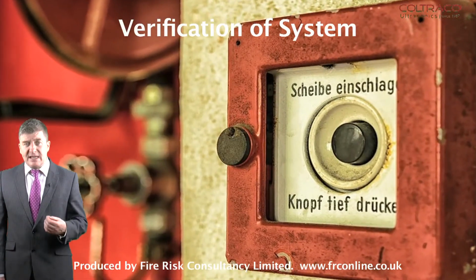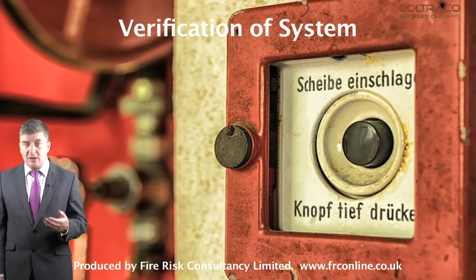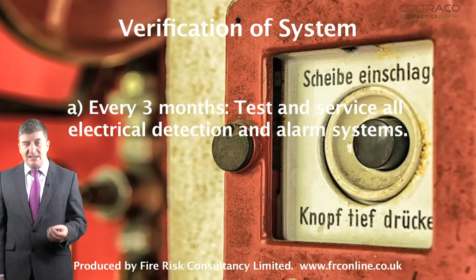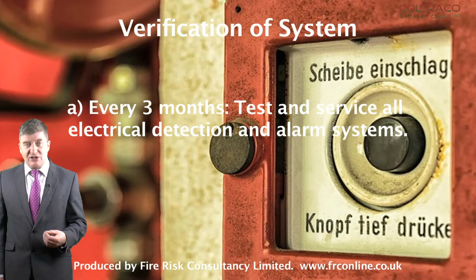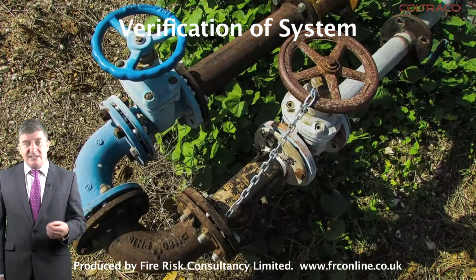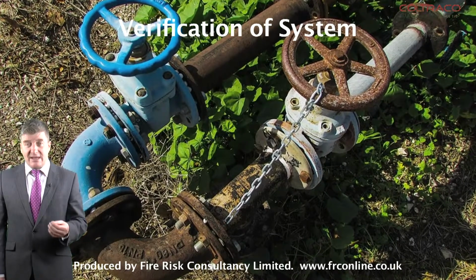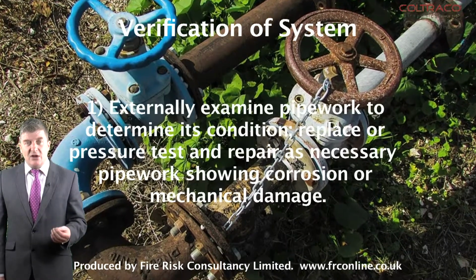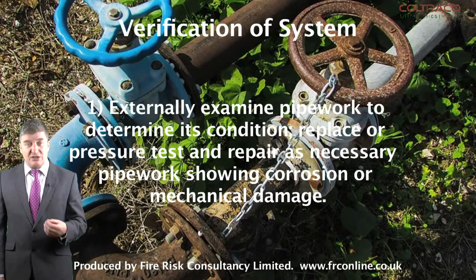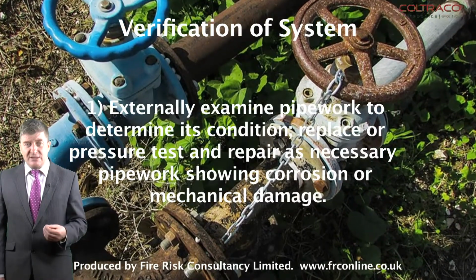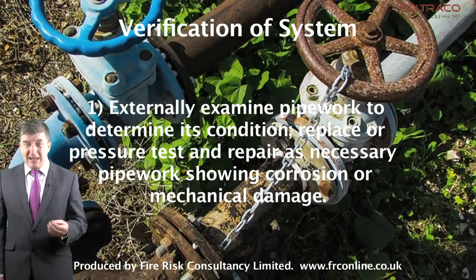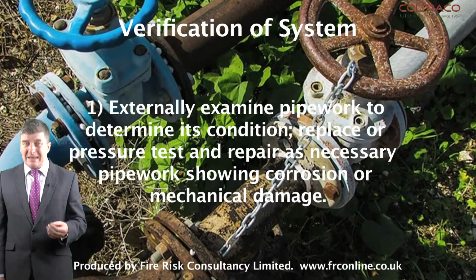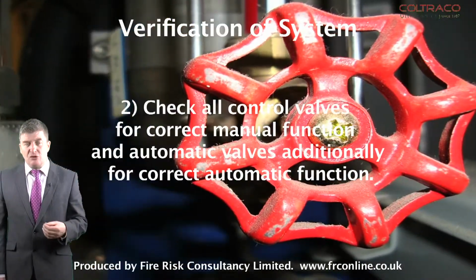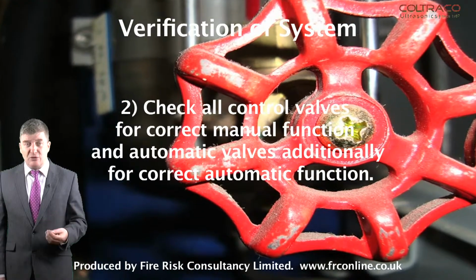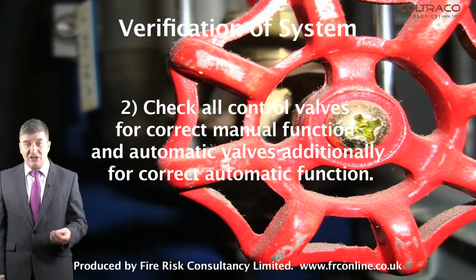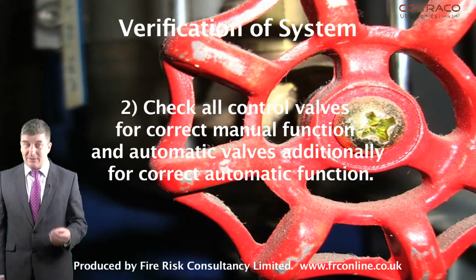A suitable procedure for verification of the system includes every 3 months test and service all electrical detection and alarm systems. Every 6 months perform the following checks and inspections. Externally examine pipework to determine its condition. Replace or pressure test and repair as necessary any pipework showing corrosion or mechanical damage. Check all control valves for correct manual function and automatic valves additionally for correct automatic function.